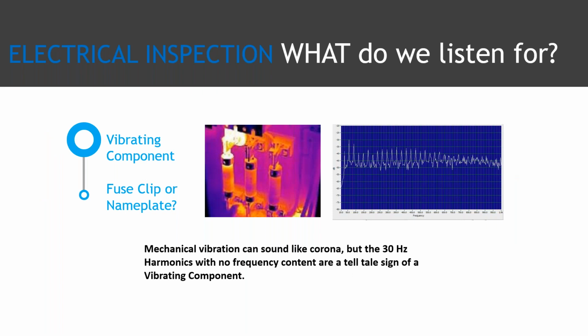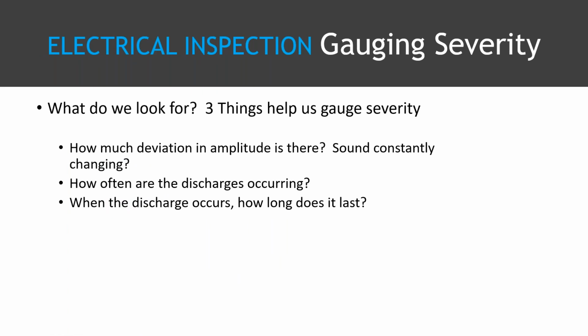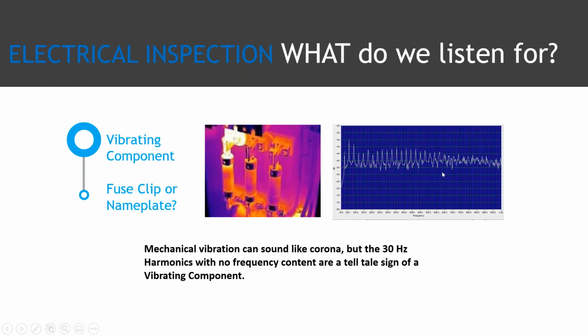Sometimes a vibrating component, whether it be a fuse clip or a nameplate, can fool you. One way to determine whether it's mechanical vibration or corona, since they sound very similar, is by looking at the FFT spectrum for where the harmonics are. In many cases you'll see either a 60 cycle or 30 cycle harmonic in the spectrum, but you won't see much frequency content in between like you did with corona.